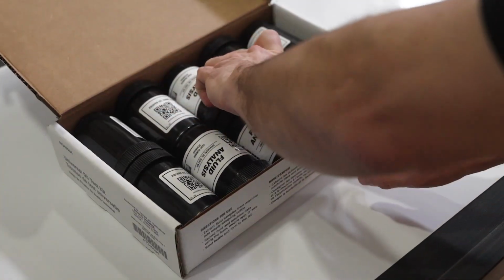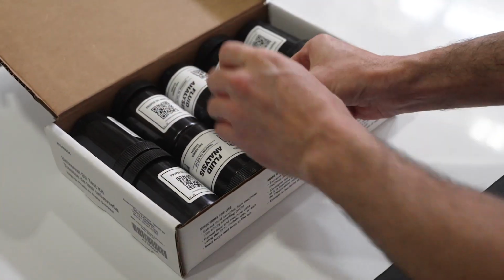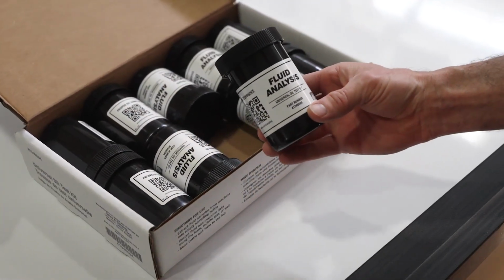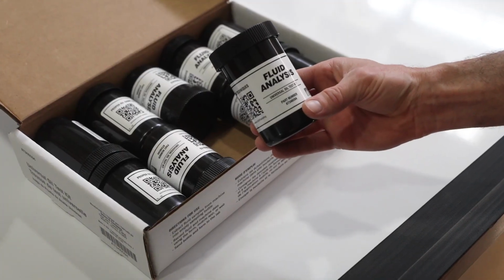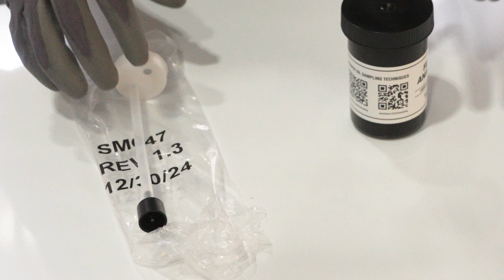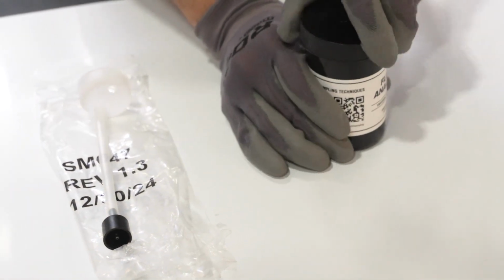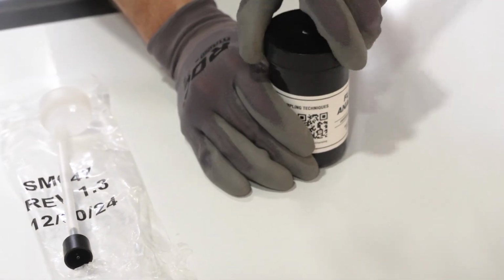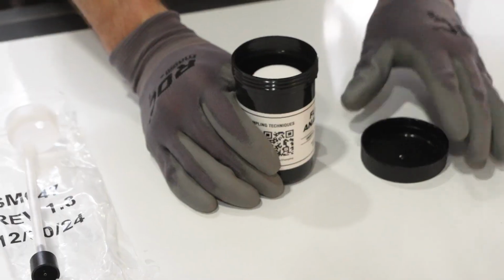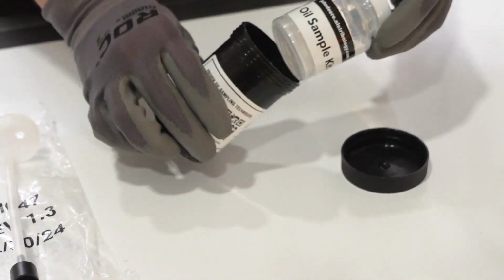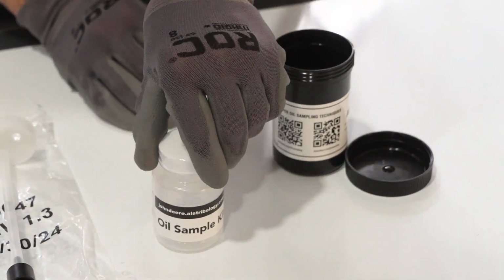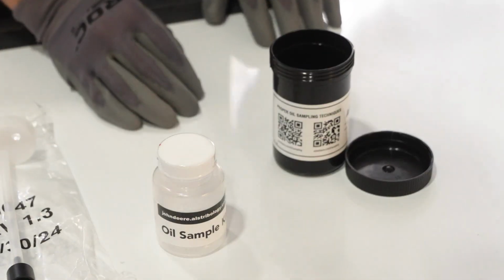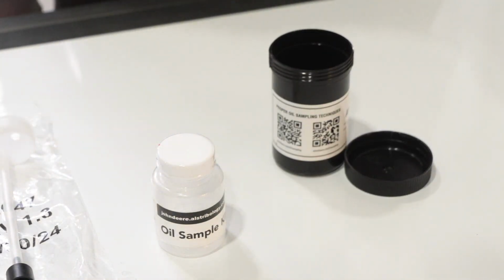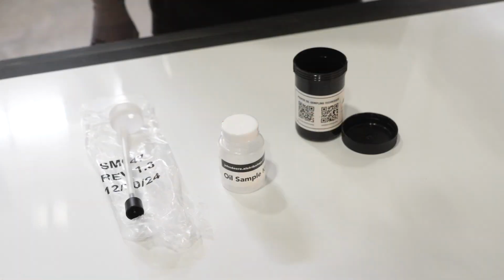Always use clean sample containers and equipment. Store sample bottles and sampling supplies so they stay clean and dry. Ideally, oil samples should be taken in a manner that is easily repeatable and effectively represents the actual condition of the oil in the equipment. When fluid samples are taken either in the shop or in the field, special care should be taken to ensure a representative sample is made and there is no cross-contamination with the environment.